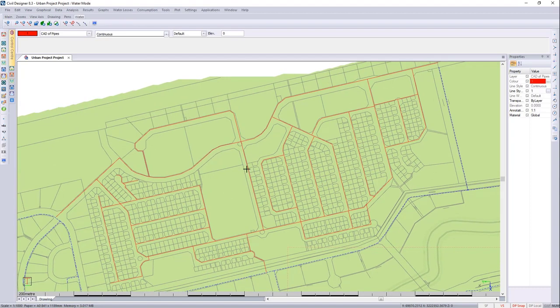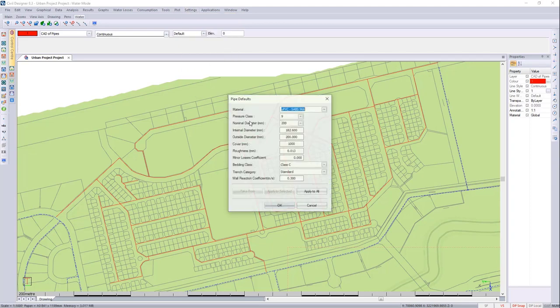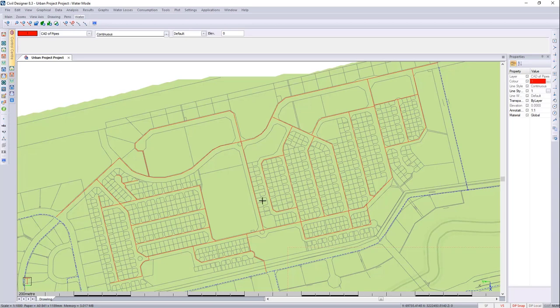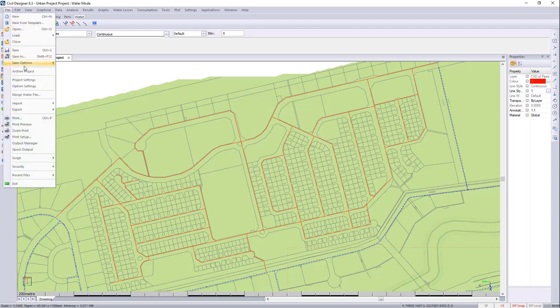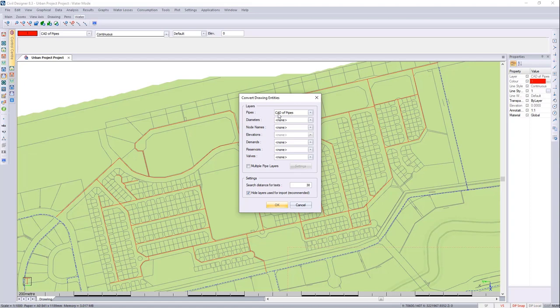Before I import them, I just want to go to my defaults and check what kind of pipes I'll be bringing in. I think for this location, they can all be the 110 diameter. Class 9 is fine for that, and a bedding class C is also perfect. I'll then go to File, Import, Convert from CAD, and I'm just going to bring the one type of pipe in, and I'll hide the layer once it's imported.